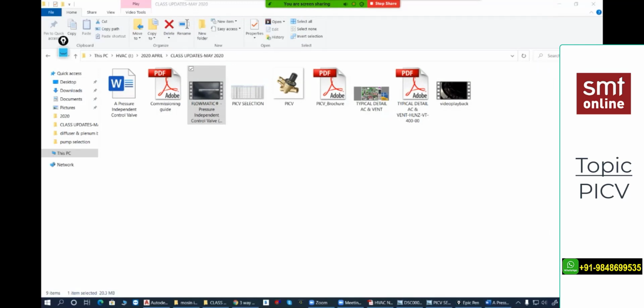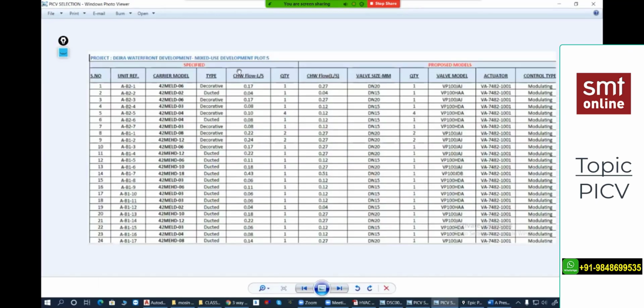So how do we do the balancing for this? First we'll install this as per the requirement, but before installing we require the selection. It is your responsibility to send the equipment schedule to the manufacturer, and this is a selection sheet. For example, you see a flow rate of 0.17 liters per second for a particular unit. These are all FCUs, decorative, ducted. If one FCU requires 0.17 liters per second, with one quantity, this is our requirement as per the equipment selection.